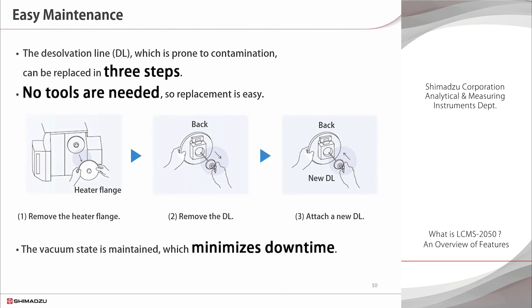Maintenance is essential to ensure stable operation of a mass spectrometer. The LC-MS 2050 is easy to maintain, so it is very user-friendly. The desolvation line can be replaced in just three steps without using tools. As a result, laboratories can operate with a minimum of system downtime.